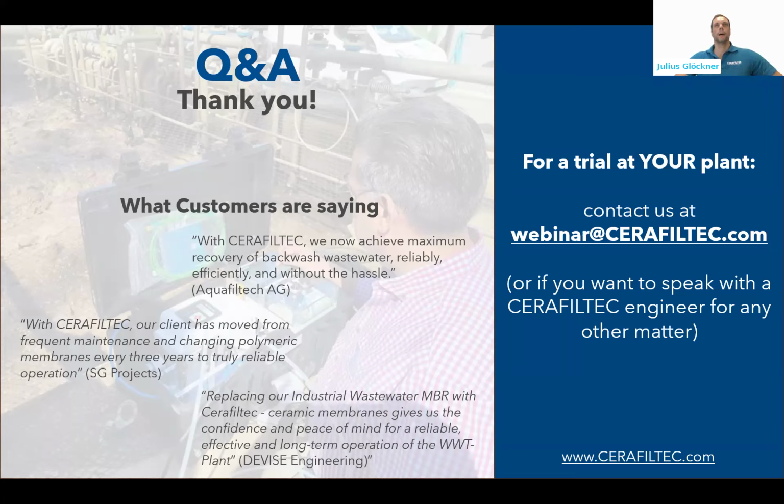We have seen that the cost of ceramic is higher compared to UF. It really depends on the application. Ceramic membranes can also be way lower in CapEx if we operate, for example, in groundwater at 400 LMH, while polymeric membranes are designed for 60, 70 LMH. So it really depends on the flux design. And oftentimes the comparison shouldn't be membrane to membrane, but what is the project CapEx in project A with polymeric membranes compared to a project with ceramic membranes?